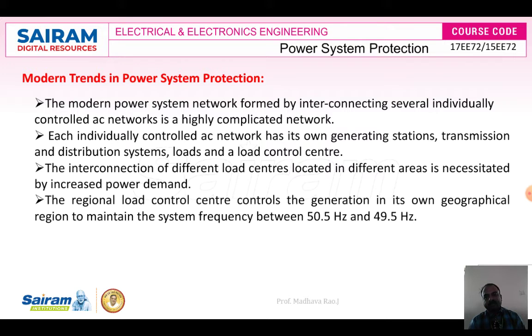The regional and load center controllers control the generation in their own geographical region to maintain the system frequency between 50.5 Hz and 49.5 Hz. The frequency is constant in AC power supplies. If the frequency varies, the speed of the alternator varies. That is what we are controlling. Commonly, the frequency range we maintain is 50.5 Hz to 49.5 Hz.